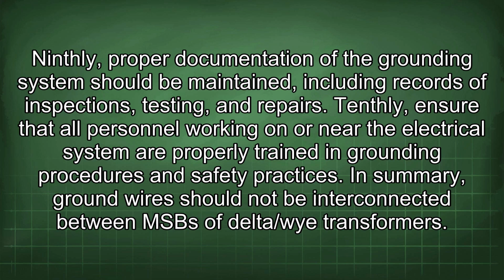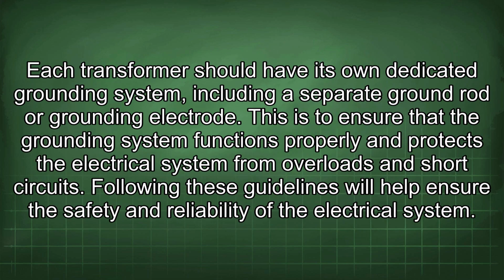Tenthly, ensure that all personnel working on or near the electrical system are properly trained in grounding procedures and safety practices. In summary, ground wires should not be interconnected between MSBs of delta/Y transformers. Each transformer should have its own dedicated grounding system, including a separate ground rod or grounding electrode. This is to ensure that the grounding system functions properly and protects the electrical system from overloads and short circuits.